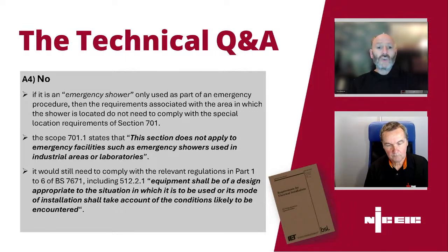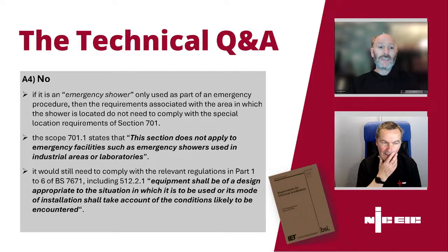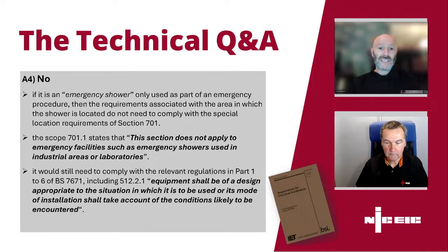Obviously, also including a regulation we're going to put out there, 512.2.1, which makes it clear equipment shall be of a design appropriate to the situation in which it is being used, or its mode of installation shall take account of the conditions likely to be encountered. In other words, is it fit for purpose for that environment? Yeah. So going back to the answer, it's a no.